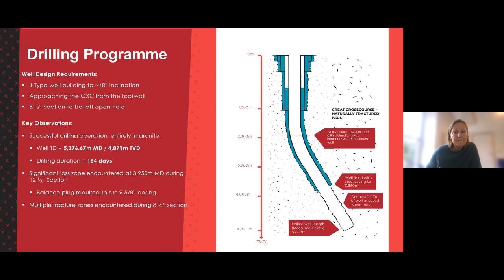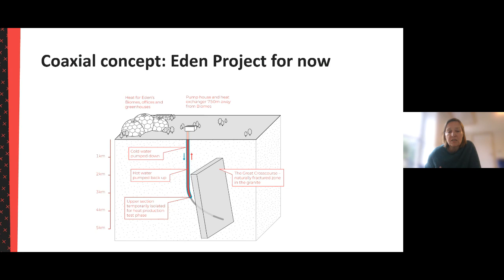At the moment we have a coaxial system. This was a feature of how the project was funded - it was European funded, and they required greenhouse gas savings from our single well, which was the maximum amount of money we could get from them. So we have one well that goes down 5,277 meters, cased to about 4 kilometers. We have a vacuum insulated tube inserted inside that well and an electrical submersible pump at about 300 meters, which sucks the hot water up from about 4 kilometers and puts it through a heat exchanger, sending it down to Eden, its biomes and its nurseries.